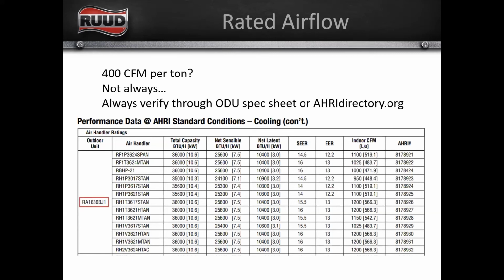So we have a RA 1636. So straight cool 16 SEER 3 ton unit outdoor. When paired with an RH1T 3617 or an RH1T 3621, so that would be a single speed constant torque or X13 air handler, 3 ton, either 17 wide or 21 inches wide. Our rated airflow is 1200 CFM. And okay, say, well, Wade, you just said 400 CFM per ton is not always. That's true, it's not always. For this matchup, it is. But for our next matchup, the match with a RH1P 3017, we're looking for 950 CFM.